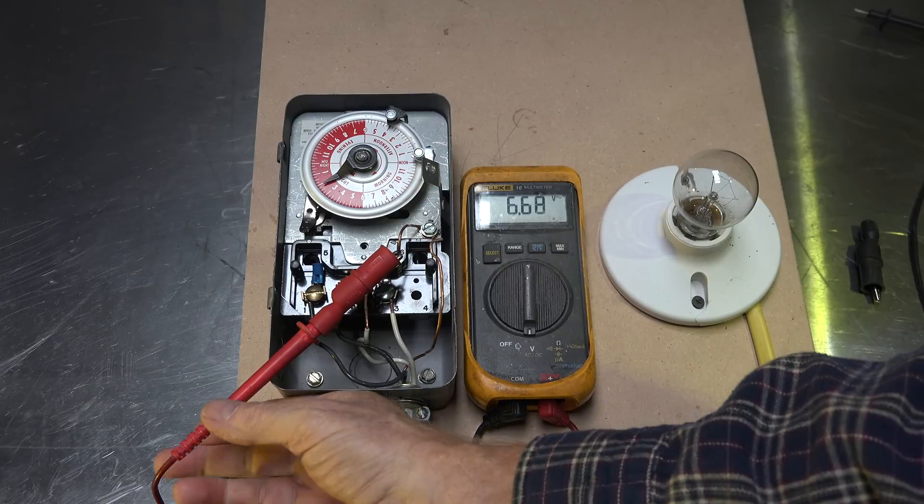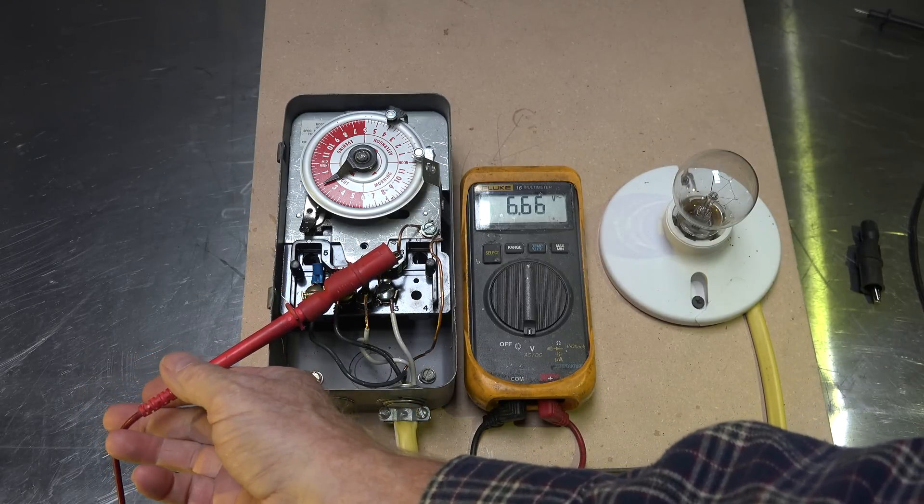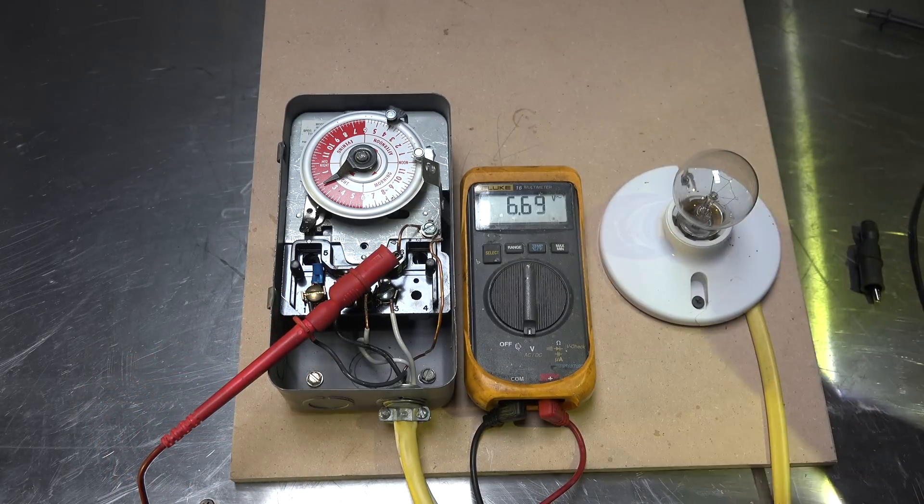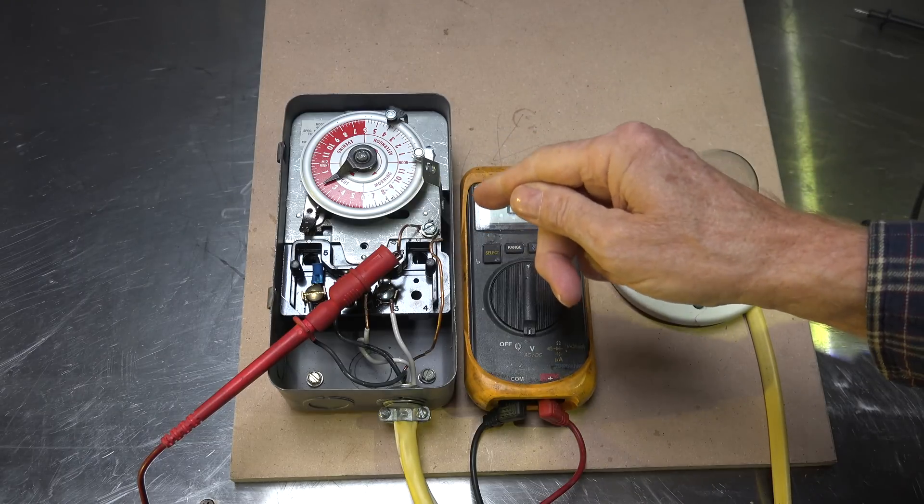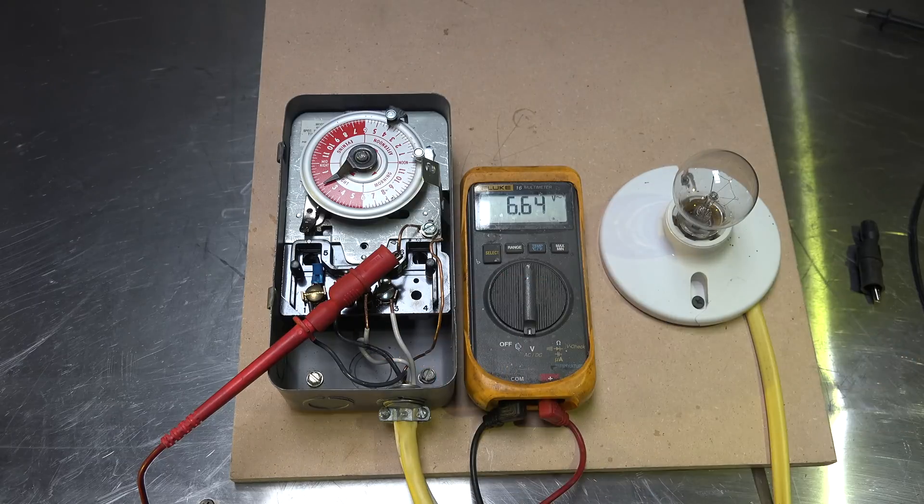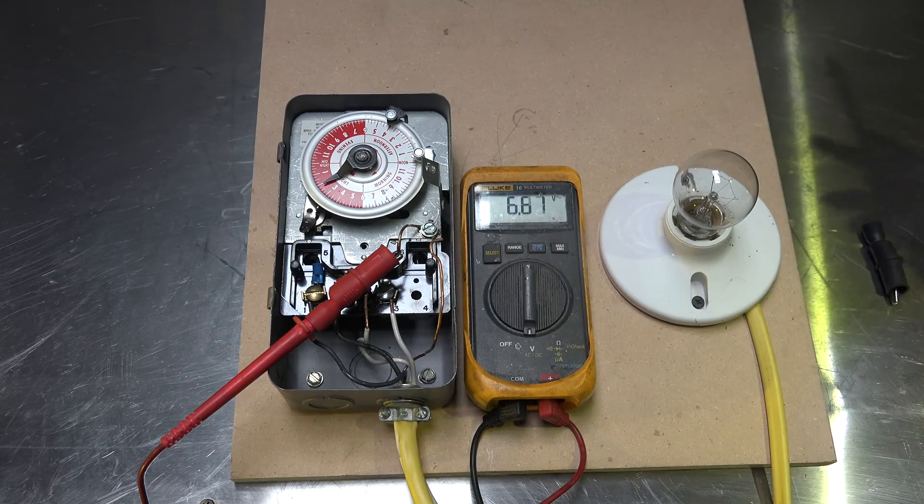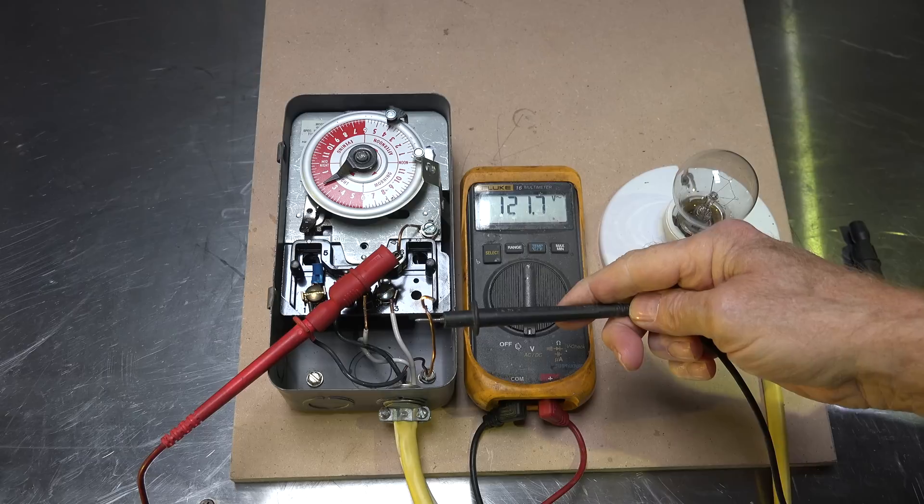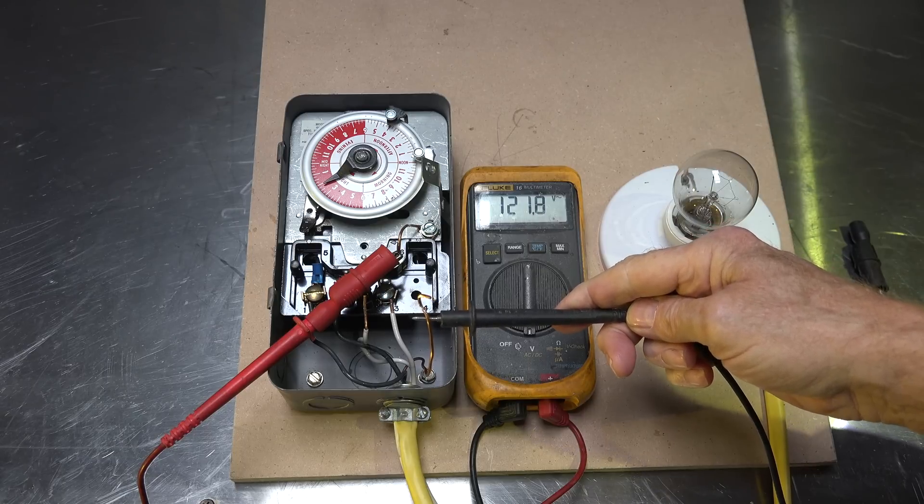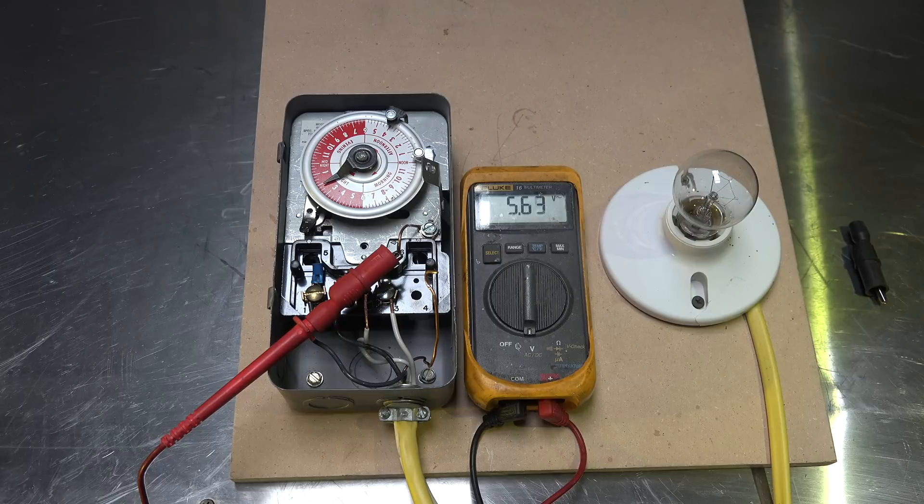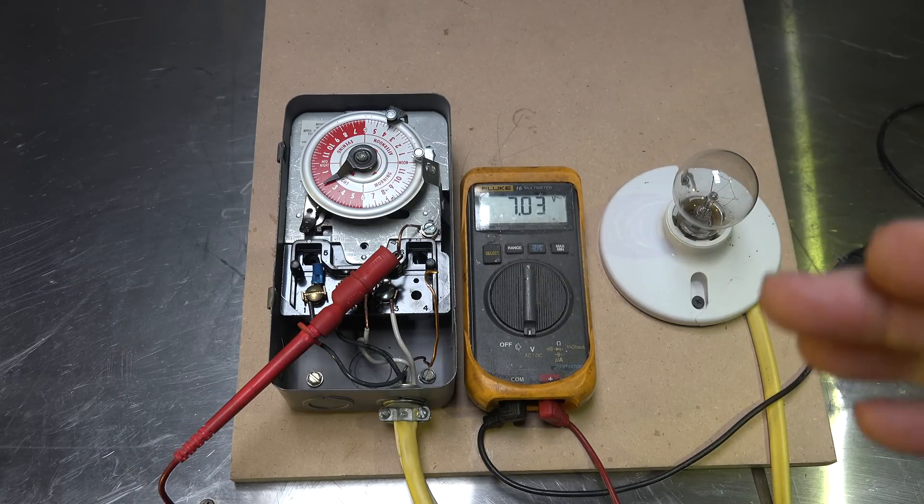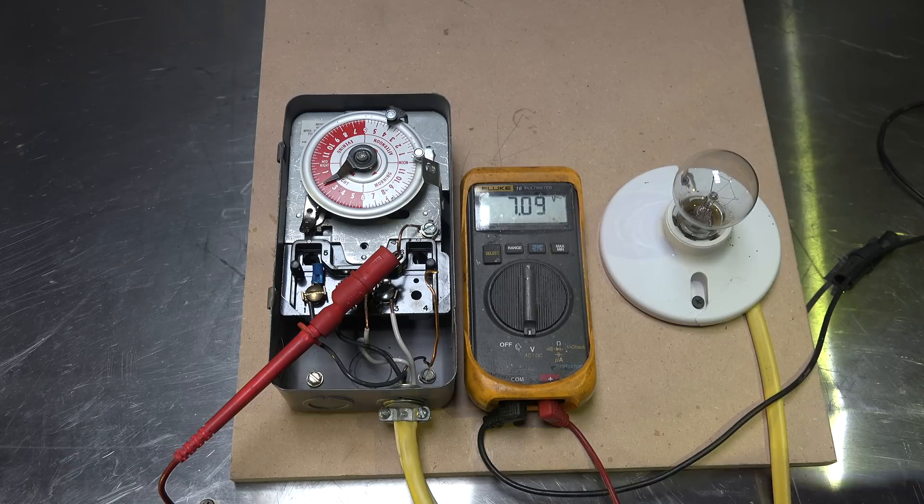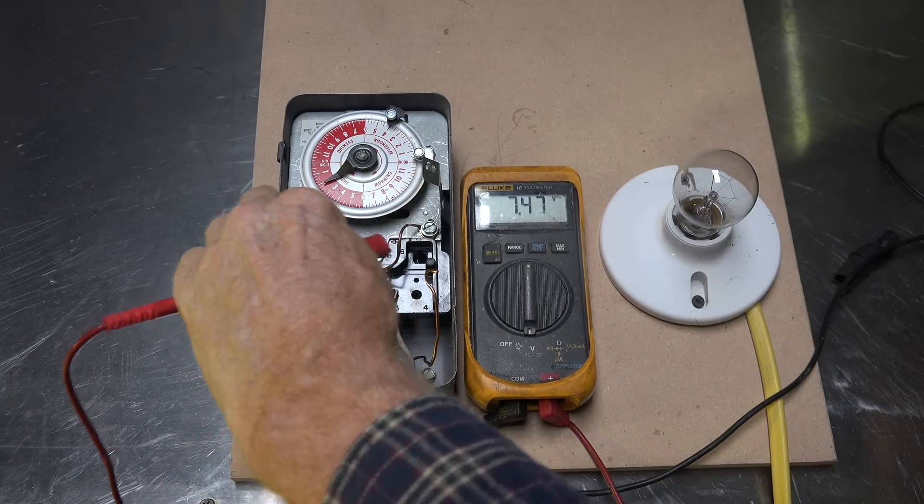Now note I've taken my other lead from the meter and put it onto the ground wire. Because this ground is disconnected and there's no connection through the neutral, then if I was to check here I would find power. That just made this box hot. The box is hot.